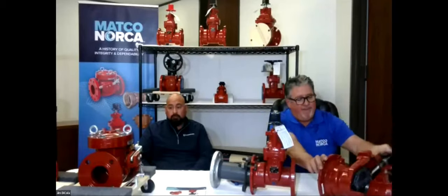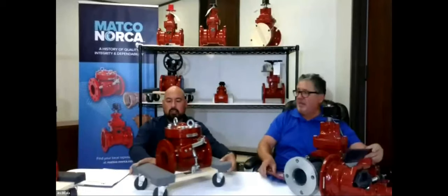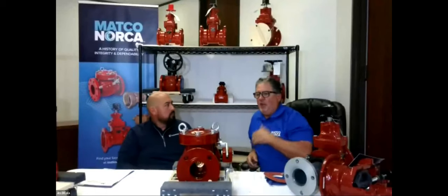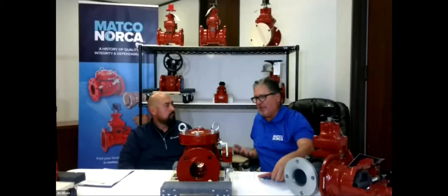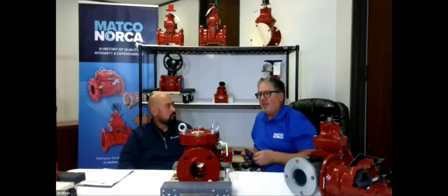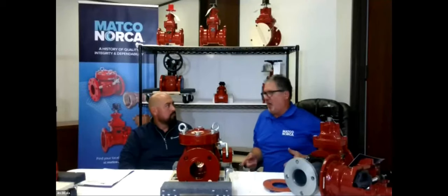Let's move to check valves. The transitions are smooth because a lift station needs gate valves, plug valves, and check valves together. This check valve is in that pump station — there's a submersible pump pumping fluids up, and then a check valve like this. This is a lever and weight check valve, used in those installations to prevent backward flow so you don't damage the pumps or get backups. On every check valve there's an arrow — on a gate valve you can mount it any way you want, but on a check valve it has to go with the flow.